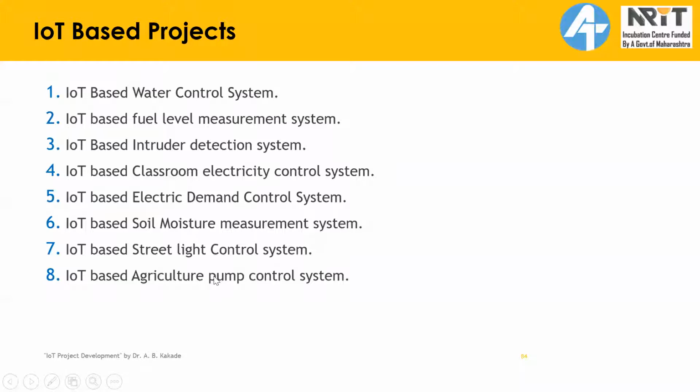The critical part is in agriculture sector, available AC voltage is not standard. Voltage may fall down to 280 volt and it may go 480, 490, something like this. So standard voltage is 440 AC volt. But in agriculture sector, many times very low voltage is available, around 280, 320 volt, something like this. So this condition must be taken into account while designing the system.